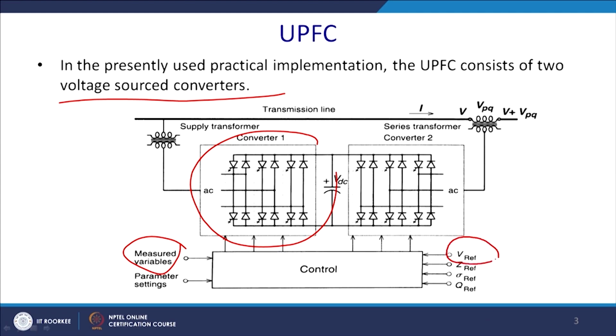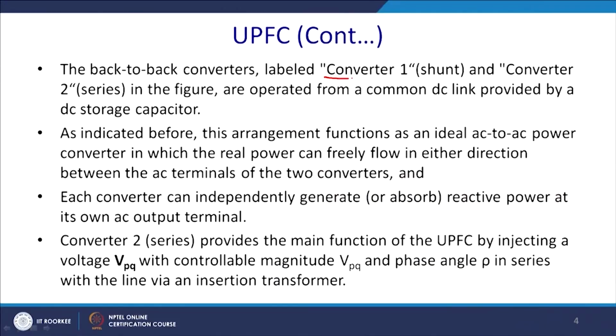We can actually set VREF, that is a voltage mode control. You can set impedance mode control, we can set sigma mode of control, and we can set reactive power mode control. So, there are different modes of operation that you can choose from this UPFC. So, what essentially the UPFC is, is a back to back converter: converter 1, that is the shunt, the right portion of it, and converter 2 in series, in the figure, are operated from a common DC link provided by the DC storage capacitor.